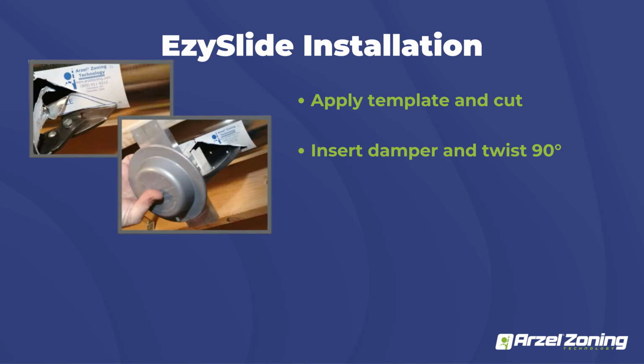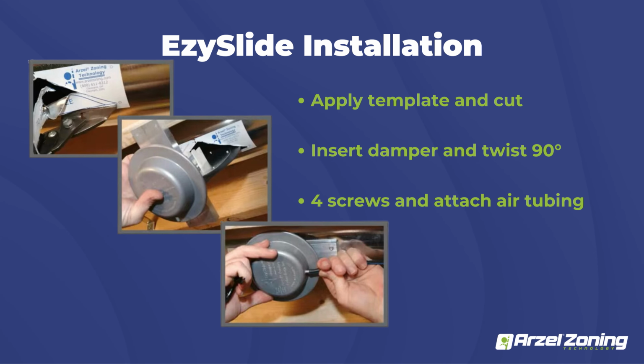Once you get that cut out, you're just going to hold your blade closed with your finger, insert it right into your duct, and then twist it 90 degrees. Once you get the damper in the ductwork, it's going to open up because that's its neutral position. That'll actually hold it in the duct, so you don't have to sit there and hold it while you're trying to get your screws in. Once you've got it in place, you just zip your 4 screws in, and that's going to hold it, and then attach your tubing to your panel.